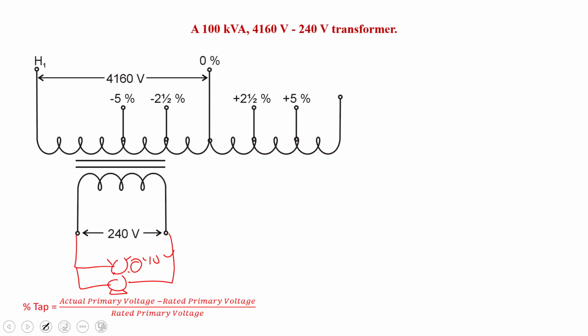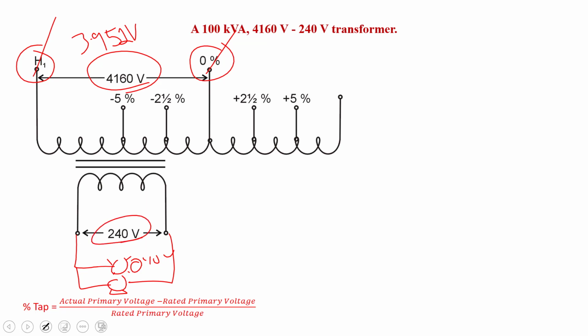Well, what happens if I don't get rated voltage on the primary? All right. So let's say that consistently in my building, I only get 3,952 volts coming in. And where I've got my 4160 terminated is on H1 and the 0% tap. That means that this transformer is expecting rated voltage of 4160, but it's not getting it. So if I put 3,952 volts on the primary, or that's all that's coming in, will I get rated voltage on the secondary? No, right?